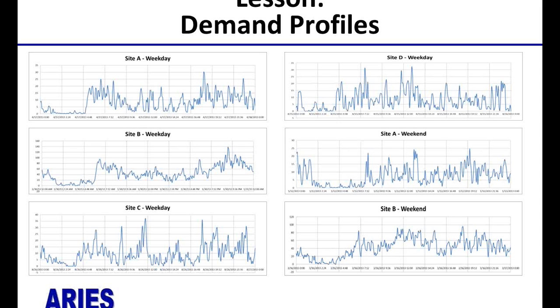and we looked at a lot of 24-hour draw profiles across the 4 buildings. If anything, there's a period of low consumption that tends to happen for a few hours in the early morning. And so this somewhat defied temperature modulation as a strategy. And it's possible that using the constant lower bound temperature satisfied people using their hot water at all points during the day.